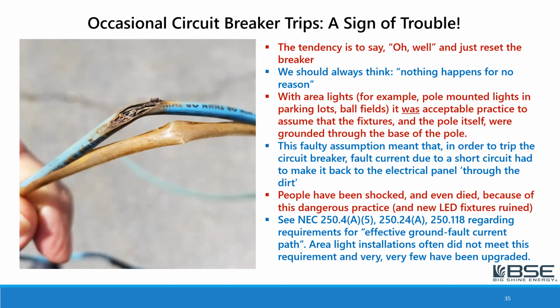And that is that it used to be acceptable practice to assume that the fixtures and the pole itself were grounded through the base of the pole. But this turns out to be a faulty assumption, because if there's a fault, in order to trip the circuit breaker back on the circuit panel, which might be inside the building, the fault current, what we call the current from the short circuit now to the pole and then therefore to the base of the pole, had to make its way back to the electrical panel through the dirt. In other words, possibly through hundreds or even thousands of feet of dirt. That resistance is so high that very often the circuit breaker would never trip. So the pole would actually be energized.